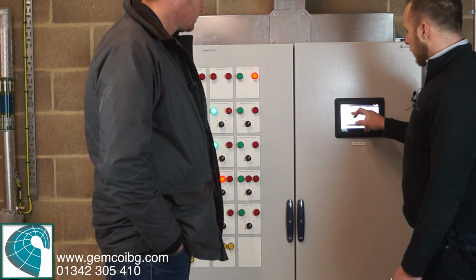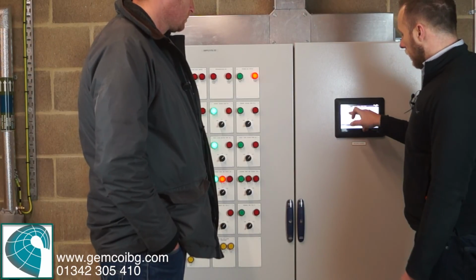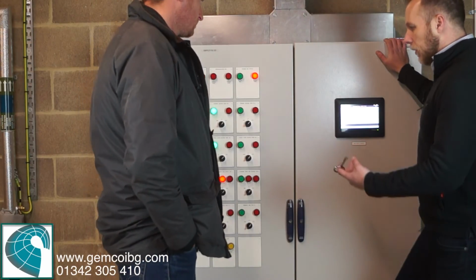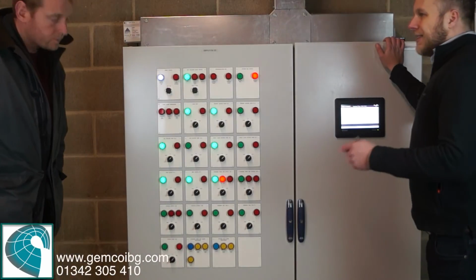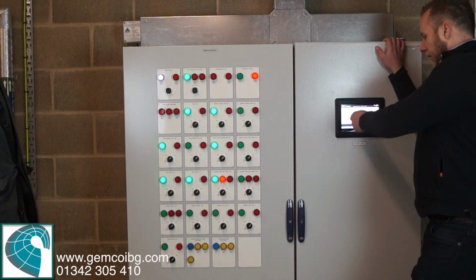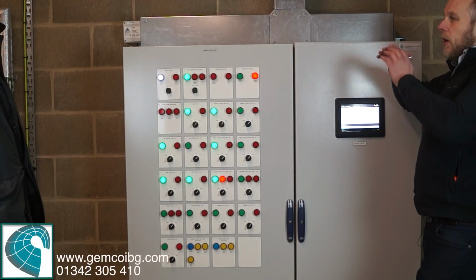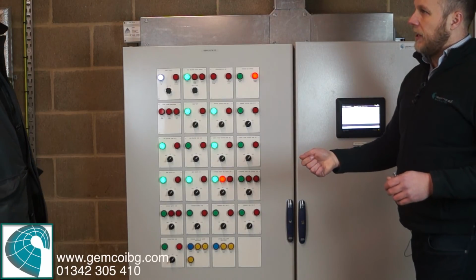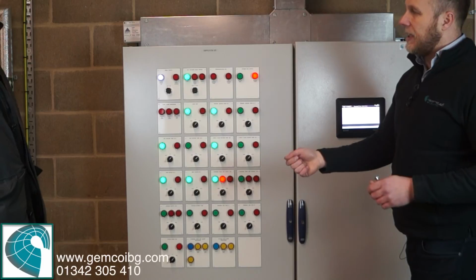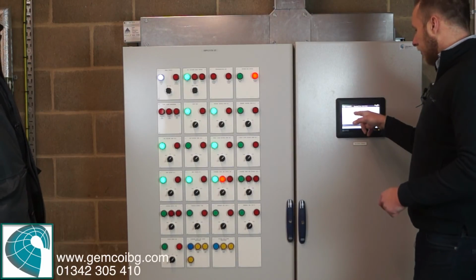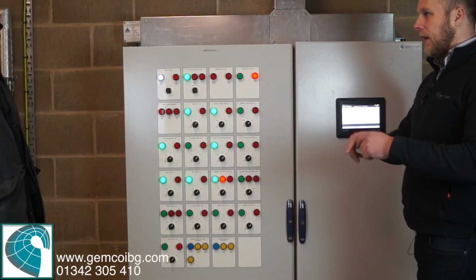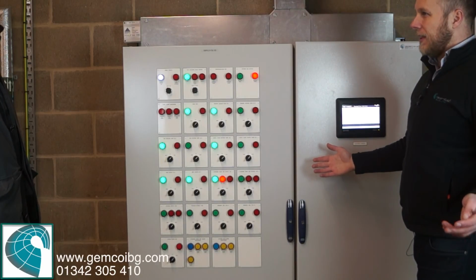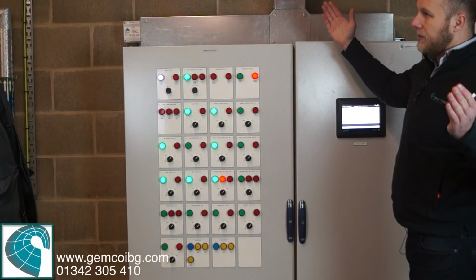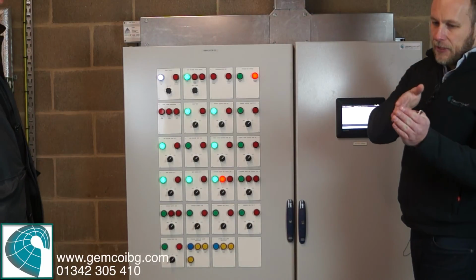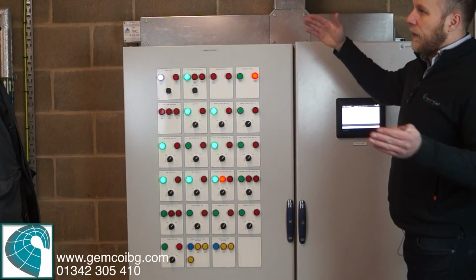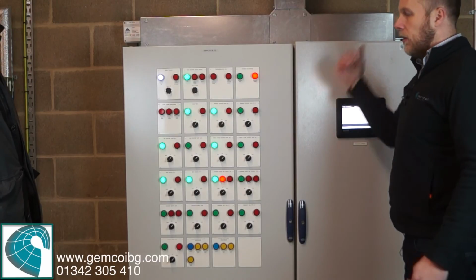Changing room, same. Pretty self-explanatory, but what I'd pay attention to is the kitchen. If they're ever going to want to use the gas, you need to make sure that that time zone is set. Although the fan won't run until they press that switch, same in the changing room, unless they activate the key switch, the fan won't run, but you need to make sure that this time zone will allow it to run when they want to run it. Does that make sense? Yeah. So you need the broad time zone so that if they come in then, it'll be available to run. Otherwise they'll turn it on, it won't run, they won't have gas.